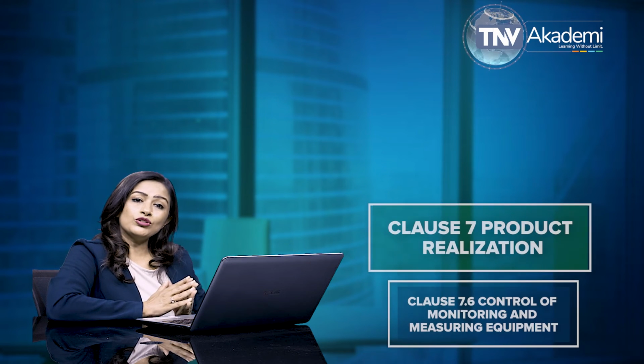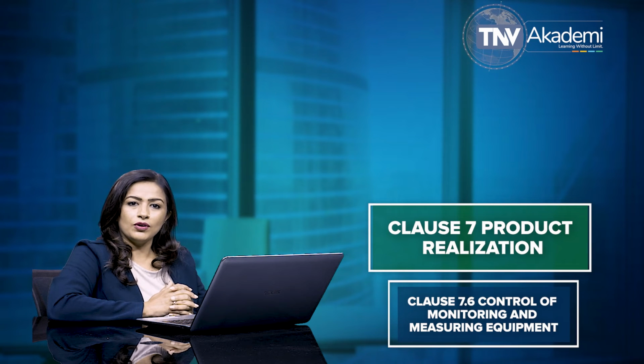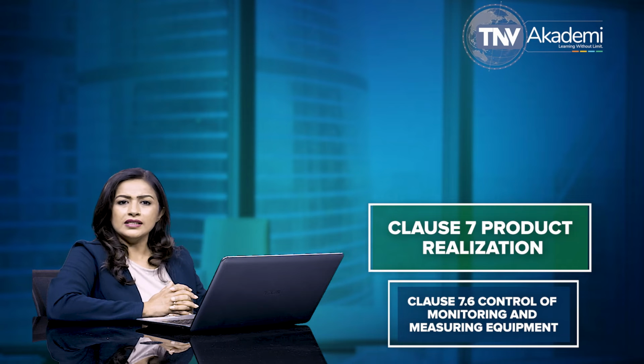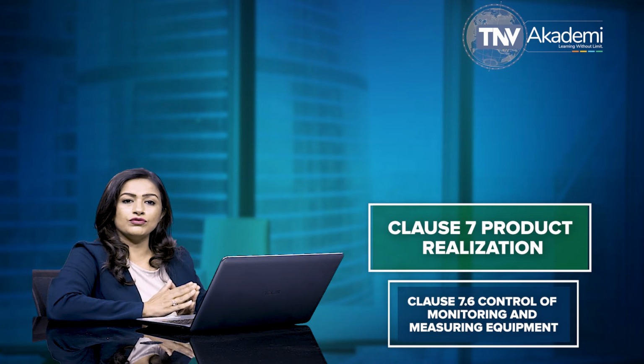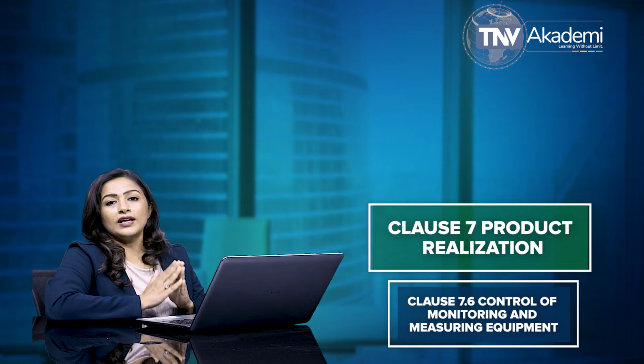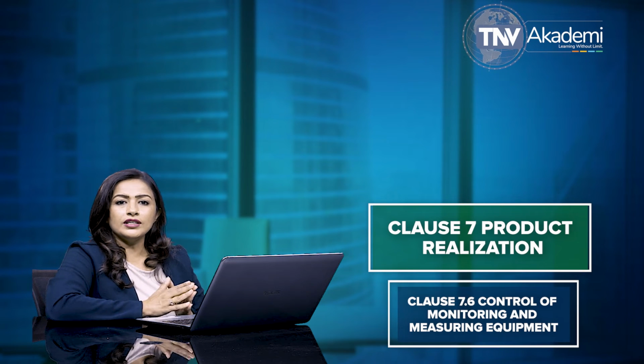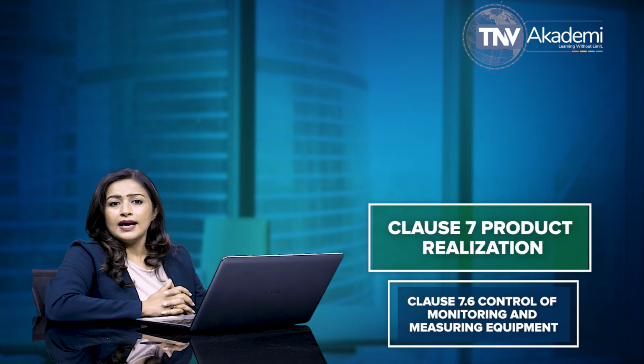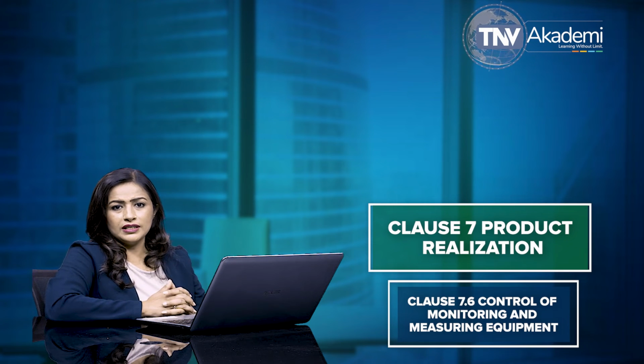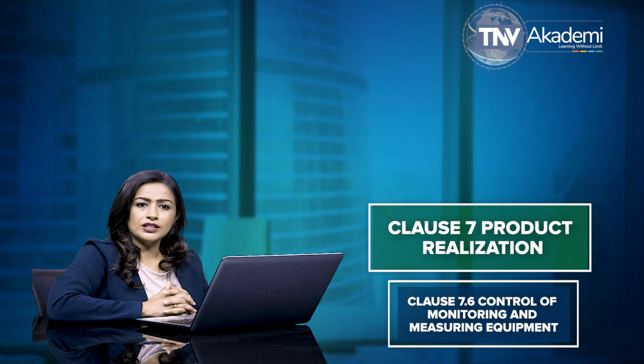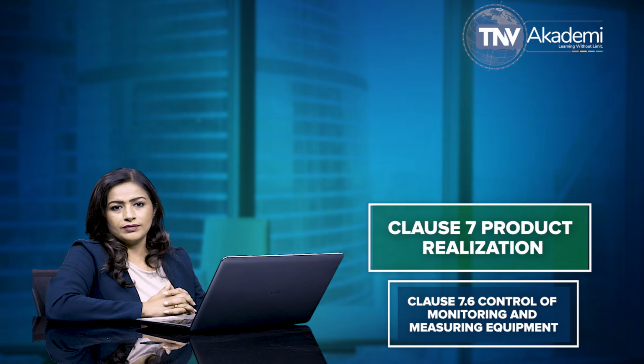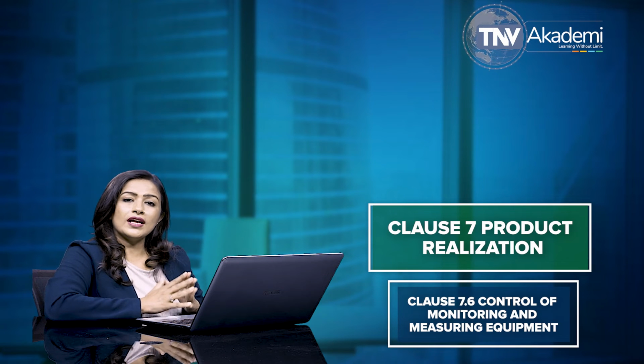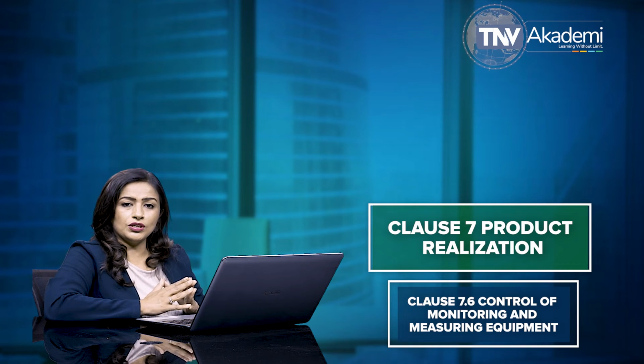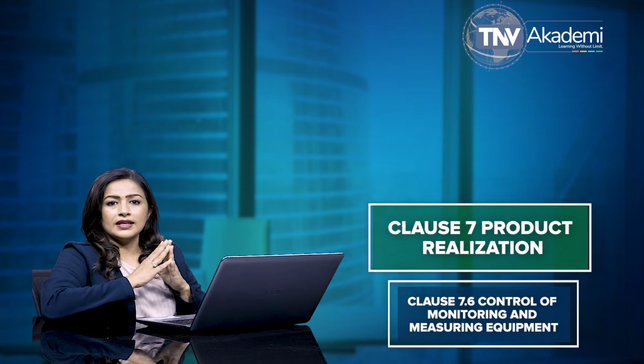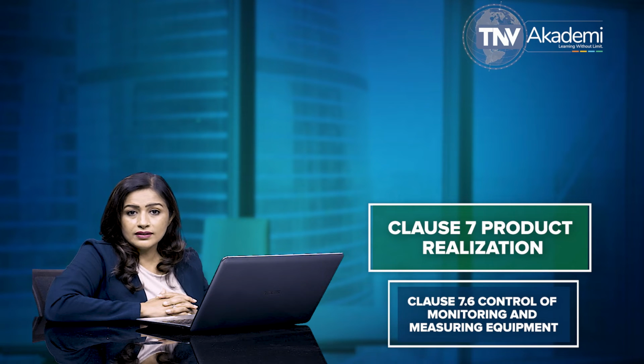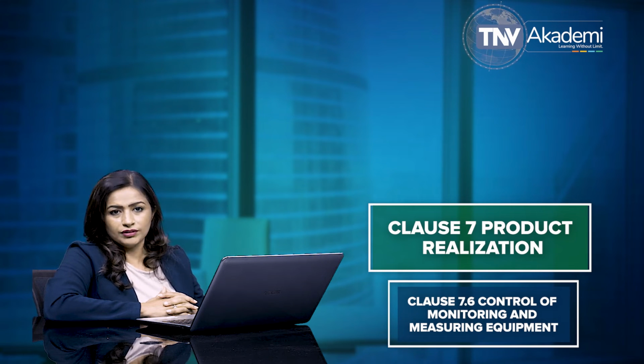Now, let us talk about clause 7.6, control of monitoring and measuring equipment. This subclause 7.6 of ISO 13485 states that the organization is required to determine the monitoring and measurement to be undertaken and the monitoring and measuring equipment needed to provide evidence of conformity of product to determined requirements. The clause says that the organization is required to document procedures to ensure that monitoring and measurement can be carried out in a manner that is consistent with the monitoring and measurement requirements.